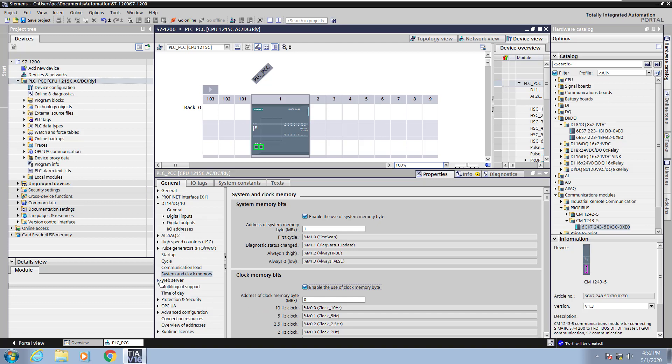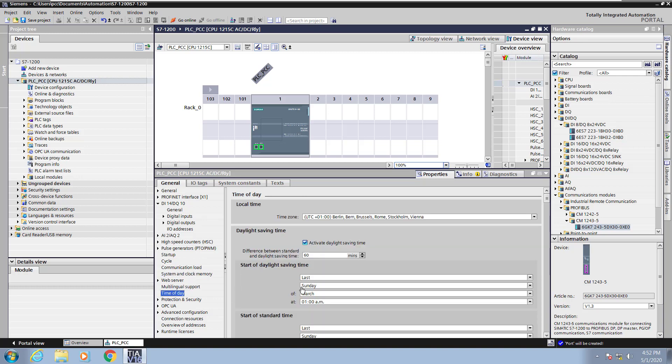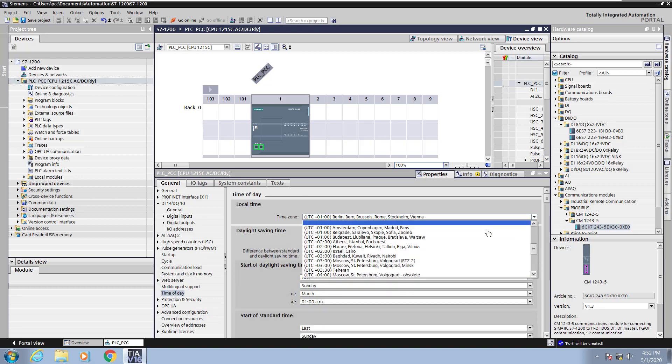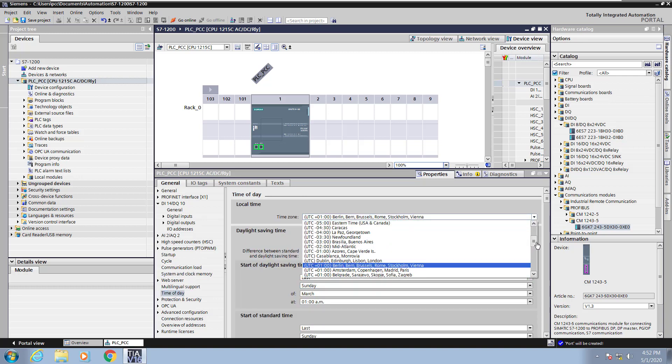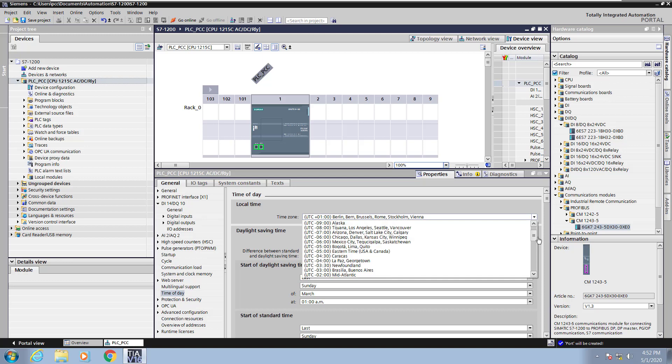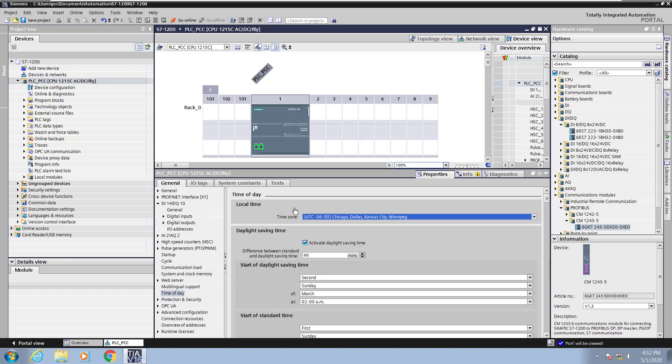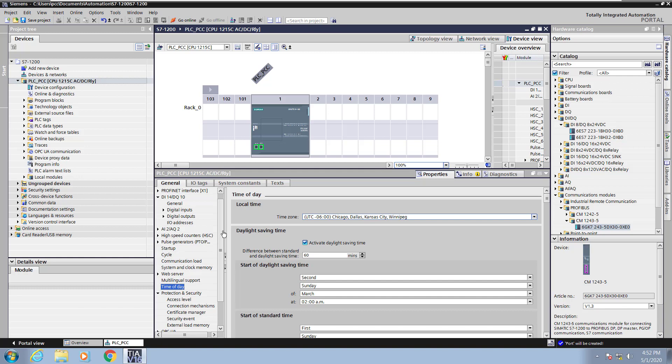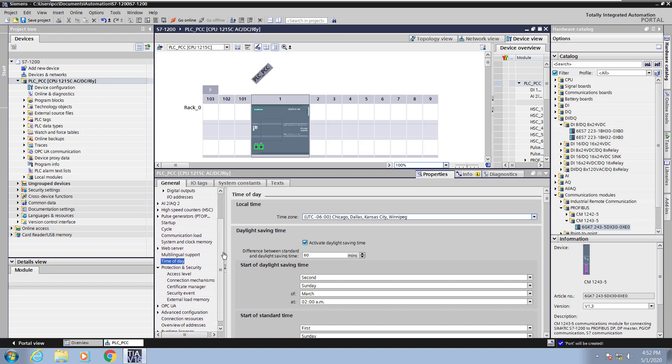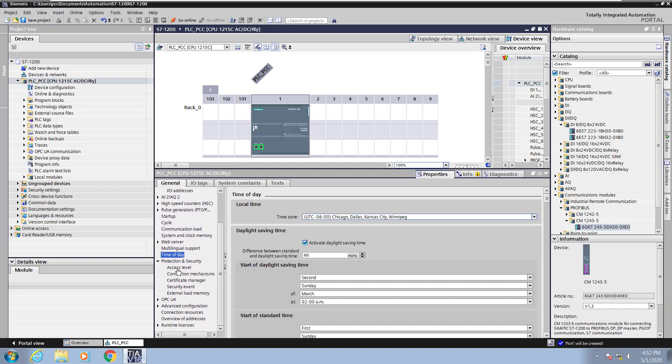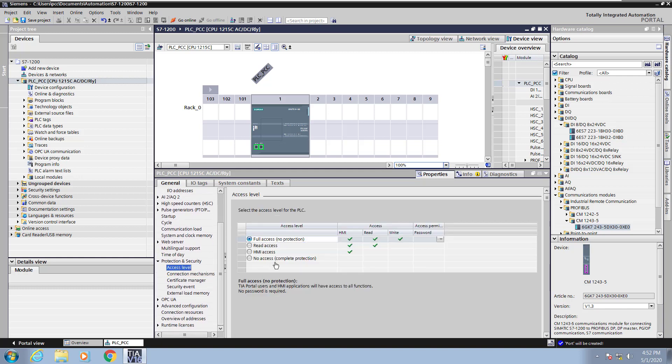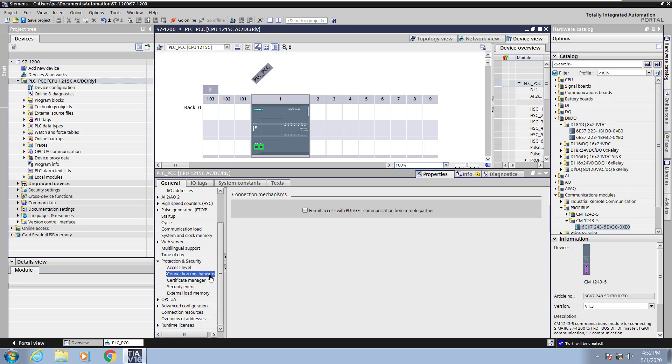The PLC also has a built-in web server that can be enabled. We also can configure the time of day so we can set our regional time zone. So I'm in the central time zone so I will pick that. Under protection and security you can set the access level of the PLC. This is where you can password protect access to the PLC. Under connection mechanisms if you want to enable like third-party communications to an OPC server as an example you'd want to enable this permit put and get interface.